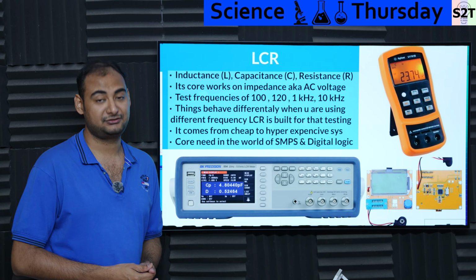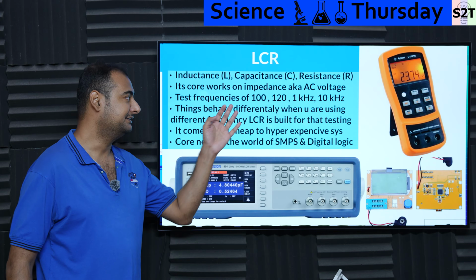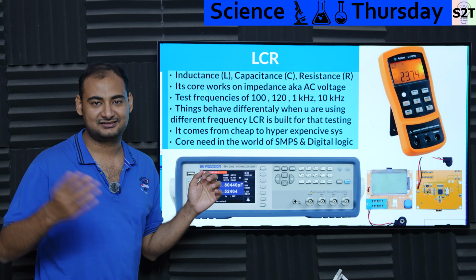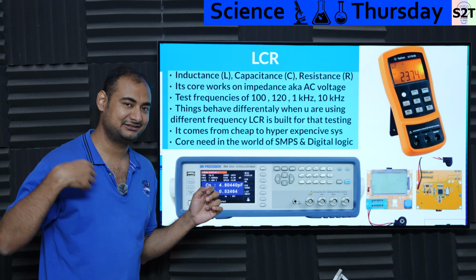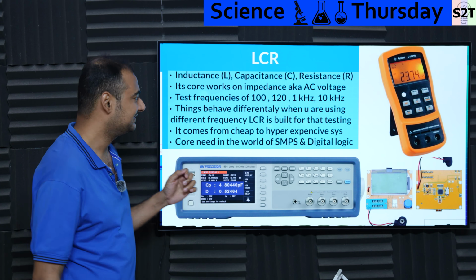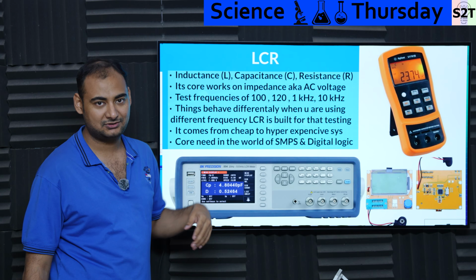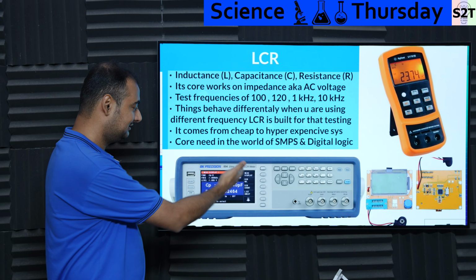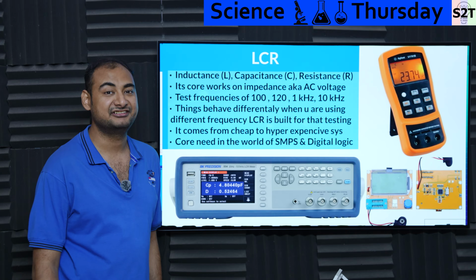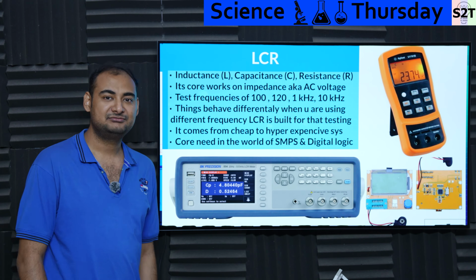As in the test frequency -- the bare minimum would be 100 hertz, 120 hertz. 100 hertz is for 50 hertz systems, 120 is for 60 hertz systems, up to 1 kilohertz to 10 kilohertz. Pro grade ones go to 500 kilohertz, like half a megahertz. And at that point, things behave differently.